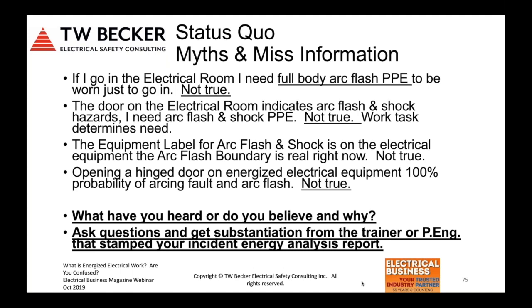The equipment label for arc flash and shock is on the electrical equipment. The arc flash boundary is real right now. It's not true. Again, the work task determines the arcing fault probability and if the arc flash boundary would be real or not. Opening a hinge door on energized electrical equipment, 100% probability of arcing fault and arc flash. I believe that's not true as well. Yet Z462 and 70E would say that any equipment conditions, arcing fault is yes. So again, we need to use the information in the standard, do our own risk assessments, and determine what work task applies to what equipment when the likelihood of occurrence would be yes.